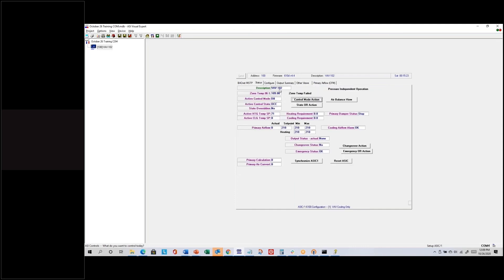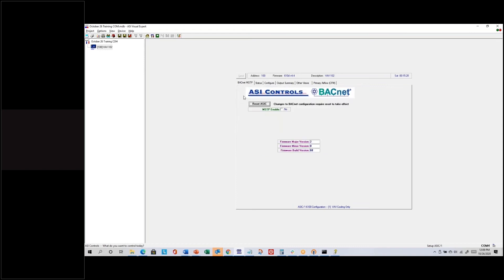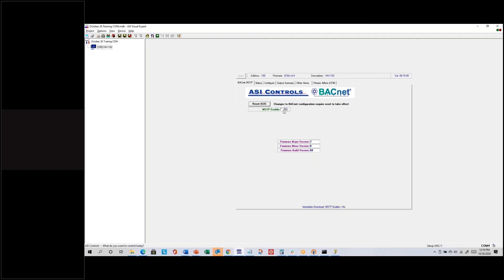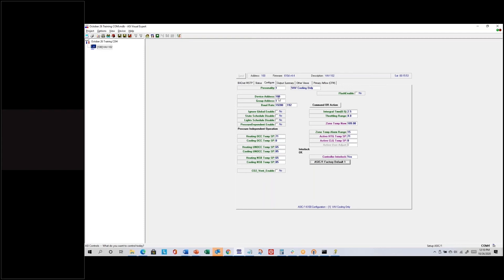That's another way to change the address — directly from the Configure tab as well as from the Find It screen. On the Status tab, I could change a description as part of initial setup. On the BACnet MSTP tab, if I wanted to enable BACnet, I could enable it and set the associated settings. Initial setup means choosing a protocol, setting the address, and configuring the associated settings — for ASI protocol that's address and baud rate on the Configure tab. Addresses need to be different; baud rates need to be the same for all controllers on the same network.